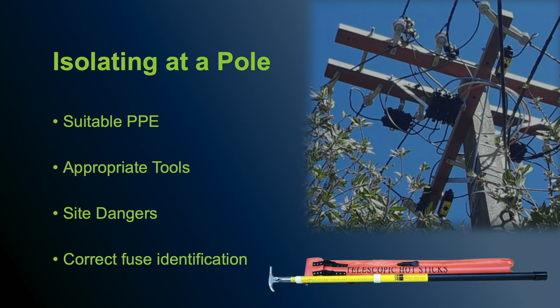The following should be considered when performing an isolation via the service fuse mounted to a power pole. Suitable PPE does need to be worn, for example, insulated gloves and leather outers, a hard hat in case your fuse falls out of the holder while you're removing it, and perhaps eye protection, as many fine objects can become dislodged while you're looking up at that fuse holder coming down.